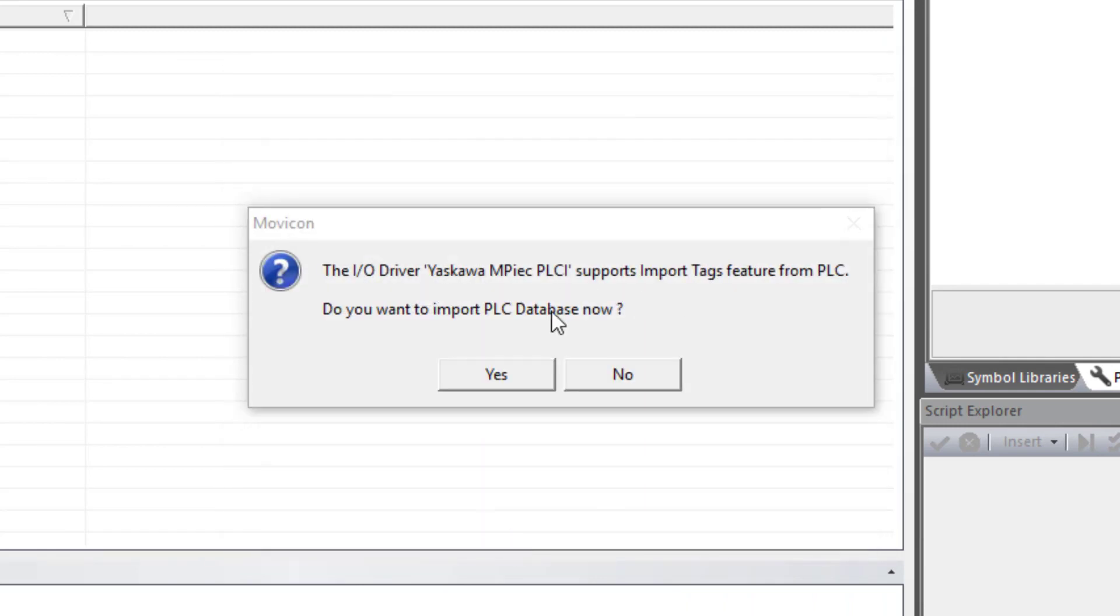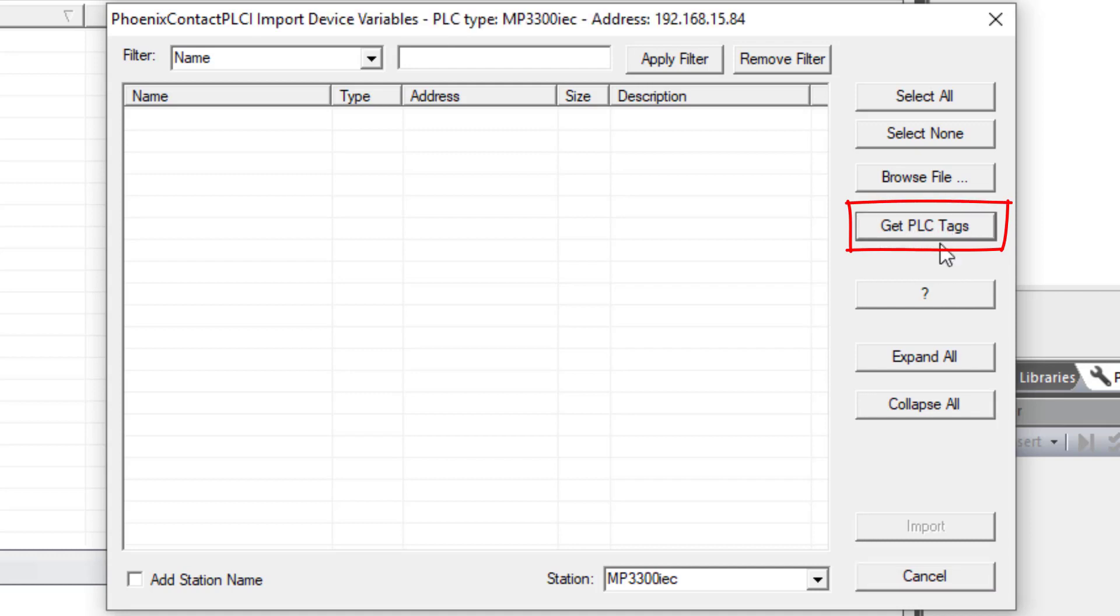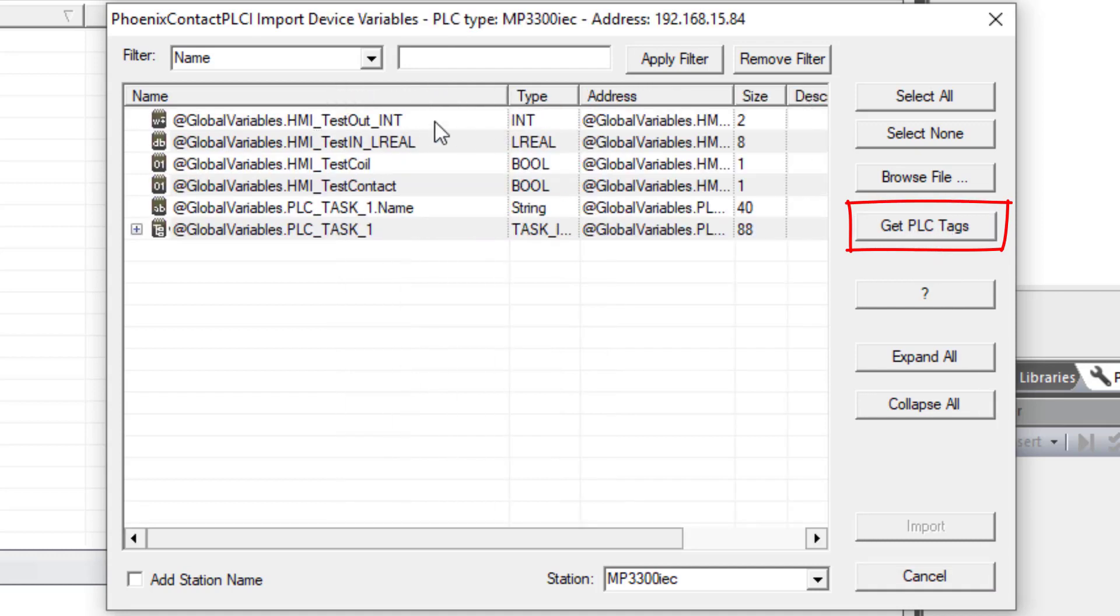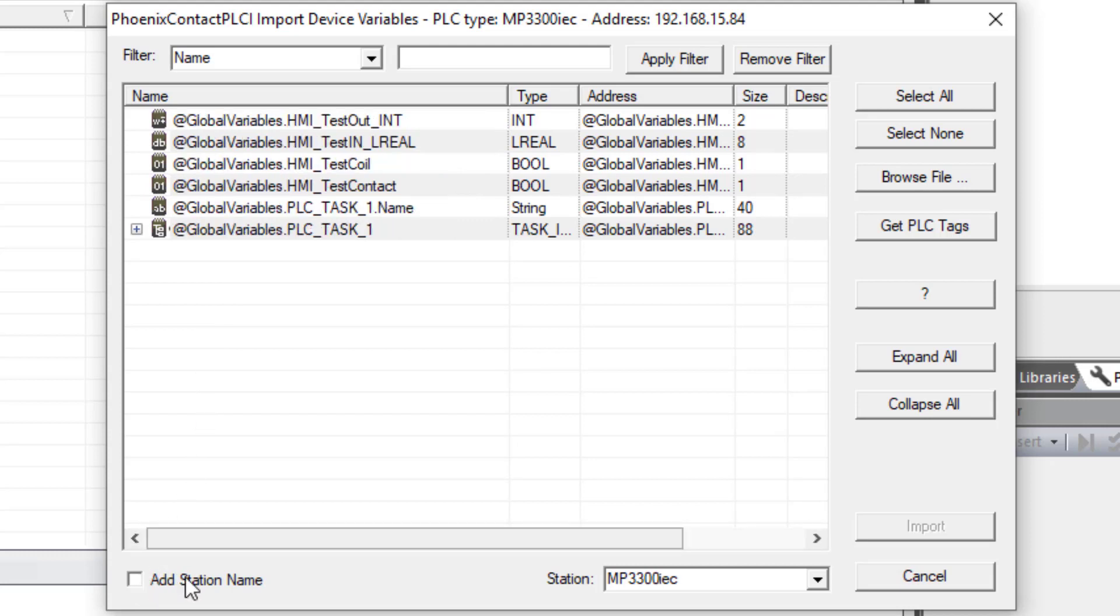Use a prompt to import tags. Yes, this is the part we wanted to get to. And since my PC is connected to the controller, the easiest thing to do is click get PLC tags. And here are all of the global variables that we had used in the project. You can see PLC task one was imported as two structures. You could add a prefix to put the name of the controller in front. If you had more than one controller, that could be helpful.